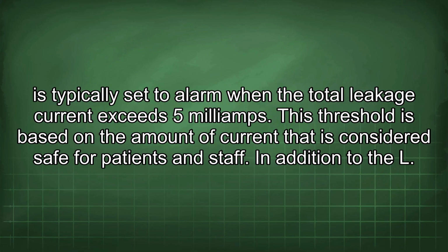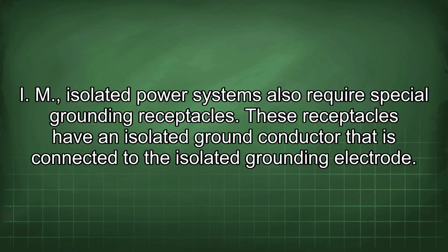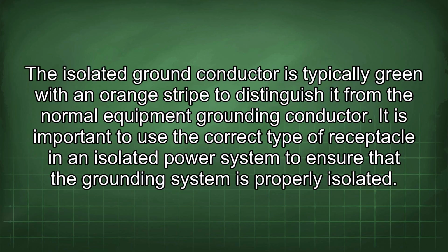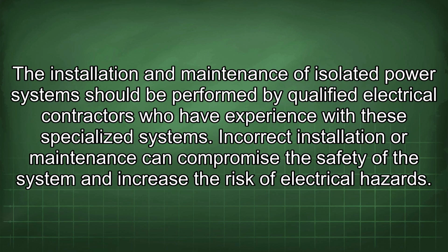In addition to the LIM, isolated power systems also require special grounding receptacles. These receptacles have an isolated ground conductor that is connected to the isolated grounding electrode. The isolated ground conductor is typically green with an orange stripe to distinguish it from the normal equipment grounding conductor. It is important to use the correct type of receptacle in an isolated power system to ensure that the grounding system is properly isolated. The installation and maintenance of isolated power systems should be performed by qualified electrical contractors who have experience with these specialized systems. Incorrect installation or maintenance can compromise the safety of the system and increase the risk of electrical hazards.